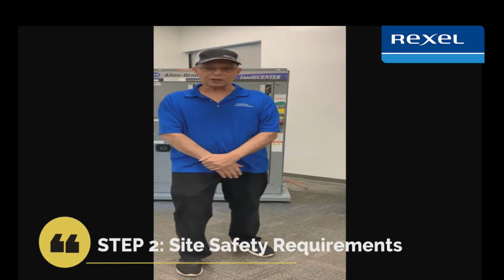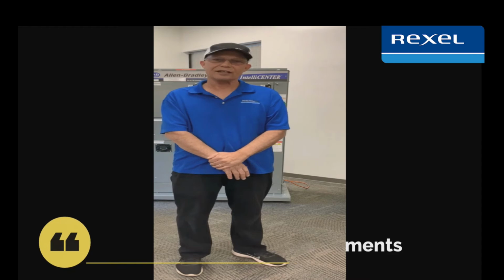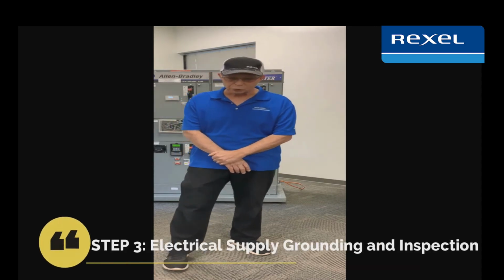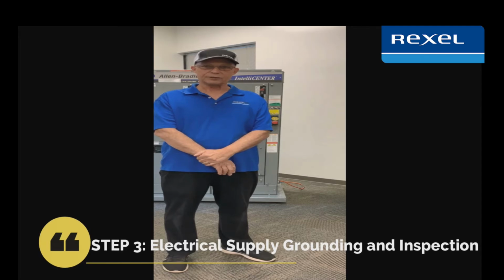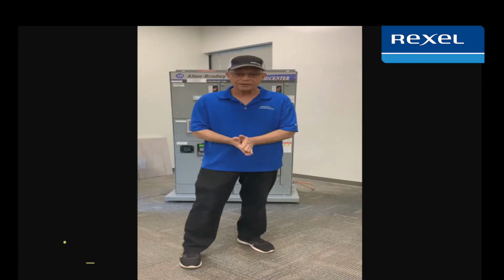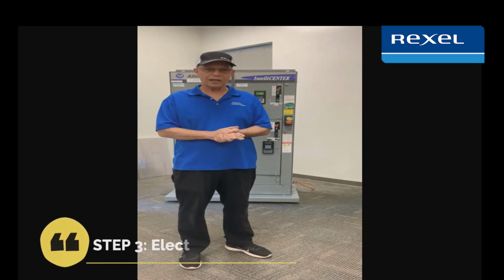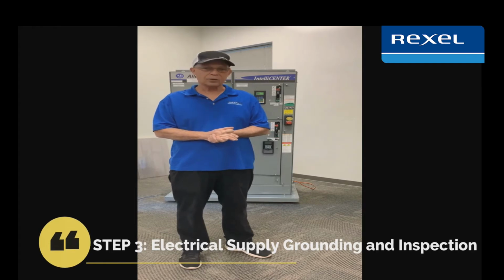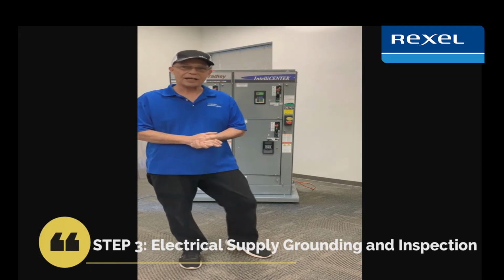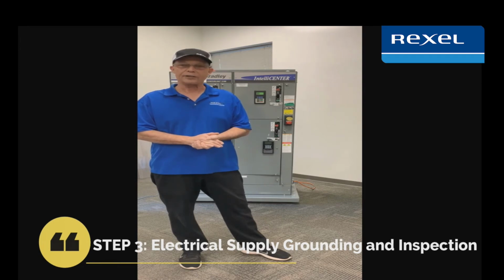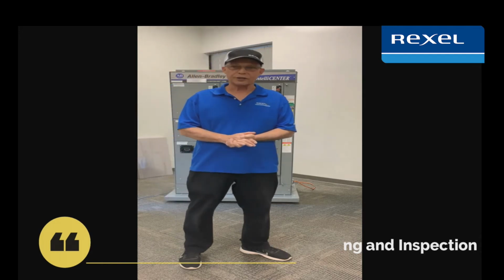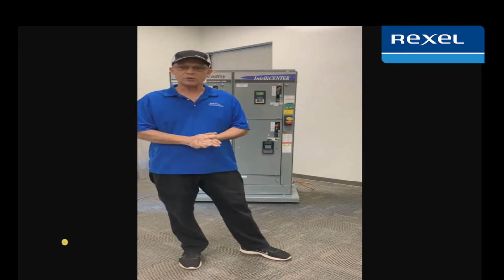Once I'm on site, we'll meet with the customer contact and go through all safety requirements, including lockout, tagout, arc flash, not to mention COVID. One of the things that we start off doing is evaluating the customer's electrical supply grounding. When I'm on site, I inspect the transformer that supplies the drive. I'm looking for grounded, ungrounded or resistive type grounds. In the case of resistive or ungrounded, I have to remove what are referred to as CAP and MOV jumpers. We commonly refer to them as power jumpers in the drive. This assures that there won't be issues with equipment becoming damaged or any EMI issues that could occur.